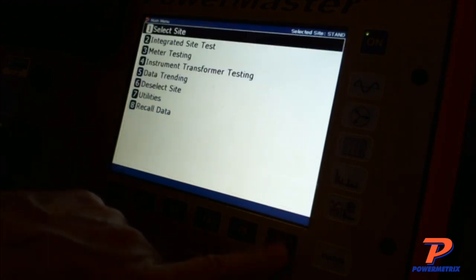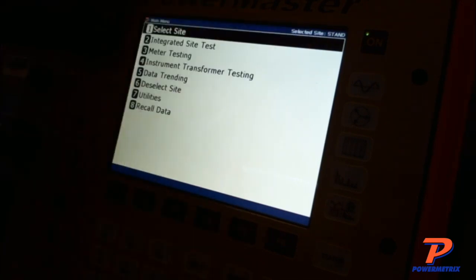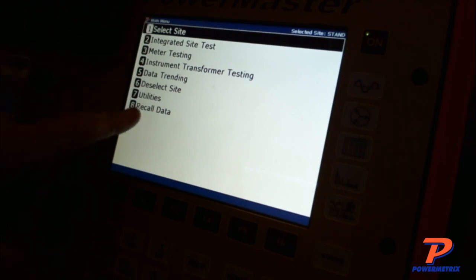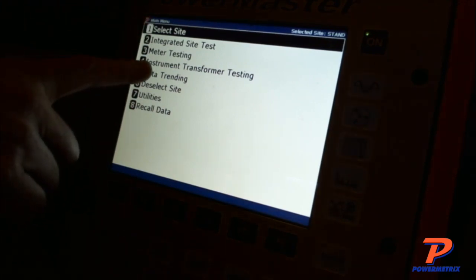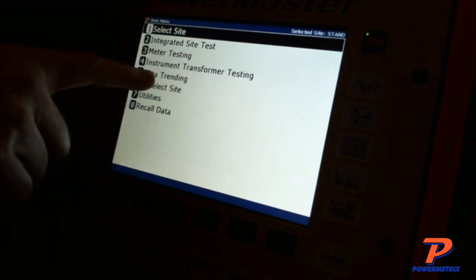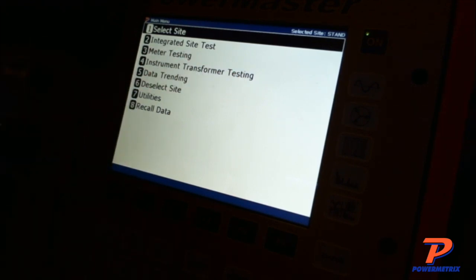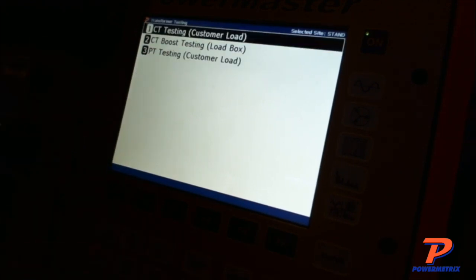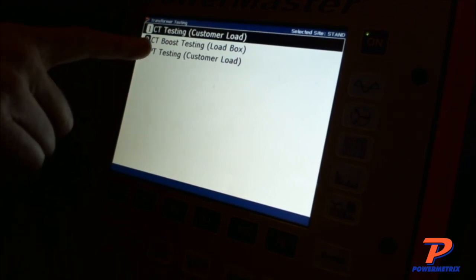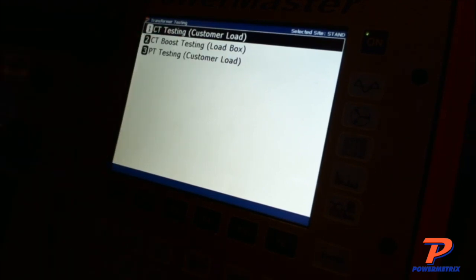Now here's where I know what site I'm on. I'm on stand, shown in the upper right hand corner like always. Now I've got my choices for that site, the different tests I can perform there. I'm going to go to number 4, instrument transformer testing, which is for testing CTs or PTs. You can see CT boost testing, load box, number 2.